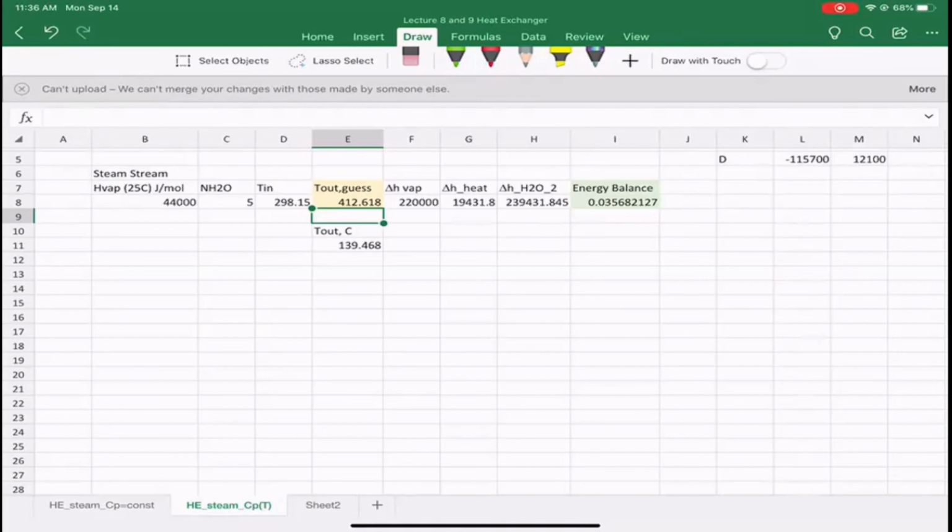So you could grossly undersize a pump. And in a large process, you might think a water pump costs $100, like one you might use at your house or in a well. But if you're talking about a large industrial-size process, you're talking tens of thousands of dollars for a large pump, plus installation costs, maintenance, and all of that kind of stuff. So here's an example where in a very practical system, you could have very, very serious ramifications for not taking the temperature change, or the heat capacity change with temperature, into consideration.